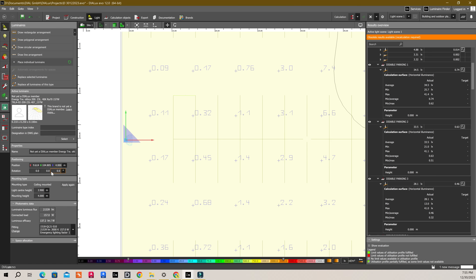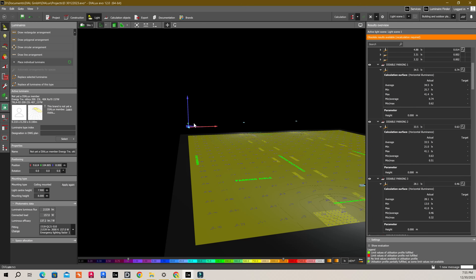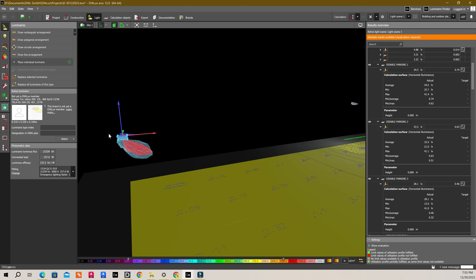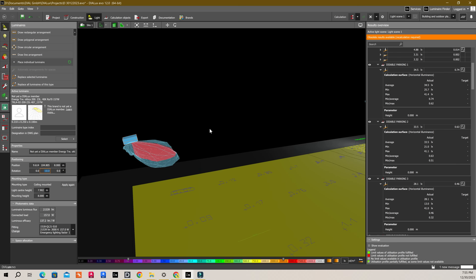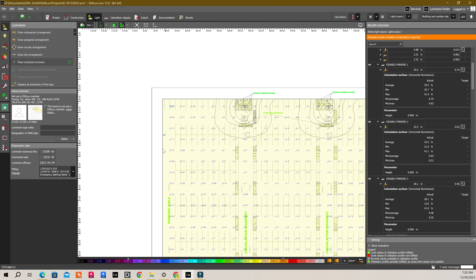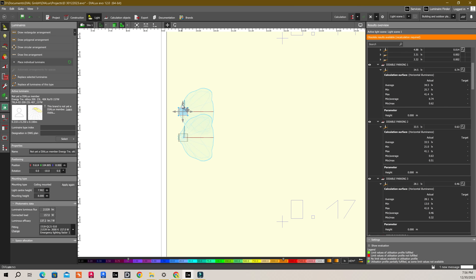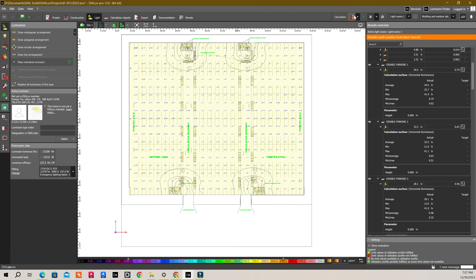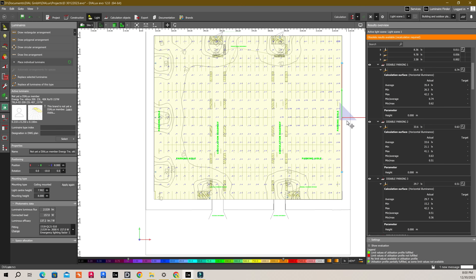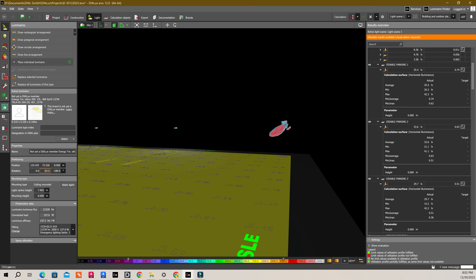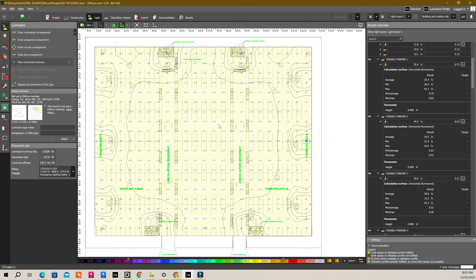I will be adding 3 lights on the extreme left side here. Set the height to 8 meters and angle to minus 10 degrees. You can recheck these parameters in the 3D view as well to make sure the inclination is correct — which is minus 10 — so it looks correct from this setup. Copy the light and paste it at equal distances for the rest of the two suitable spots, one on the top and one on the bottom as well. We now have 3 lights on the left side with a maximum distance of 32 meters between them. Copy all these 3 light fittings on the left side and paste them to the right side, rechecking the height, rotation and tilt.